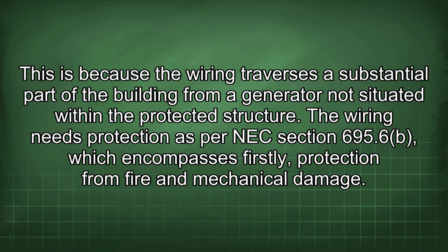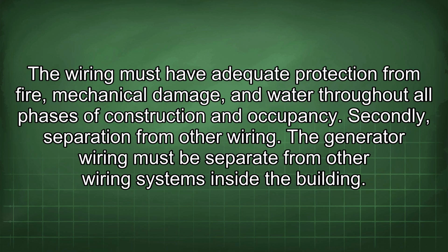695.6, which encompasses firstly protection from fire and mechanical damage. The wiring must have adequate protection from fire, mechanical damage, and water throughout all phases of construction and occupancy. Secondly, separation from other wiring. The generator wiring must be separate from other wiring systems inside the building.